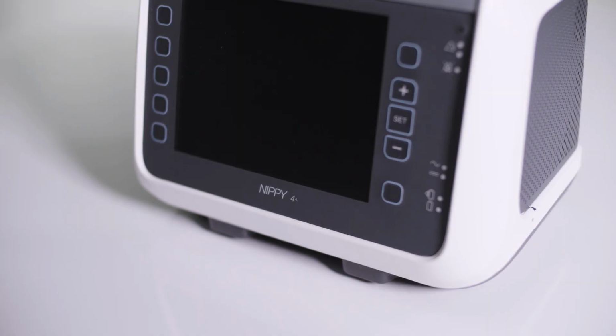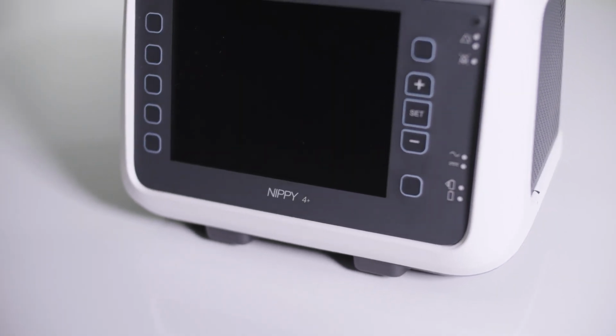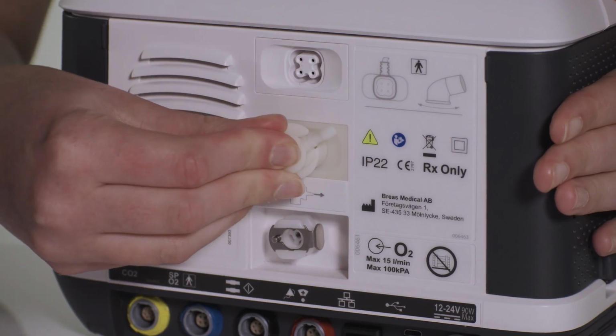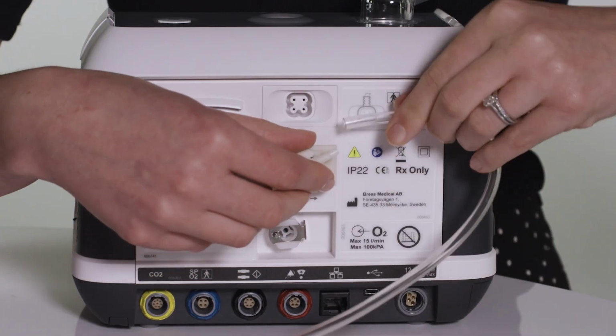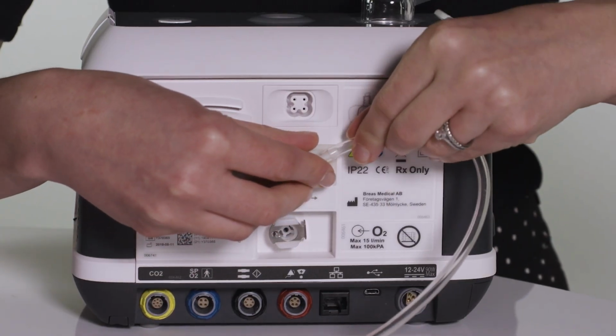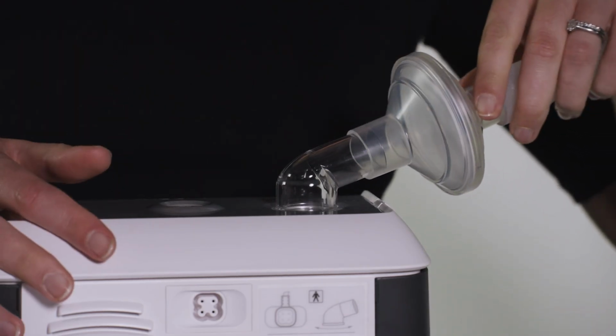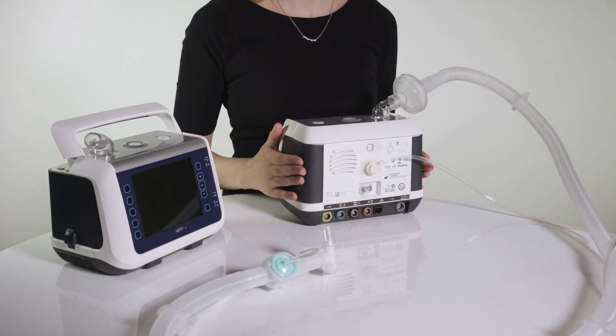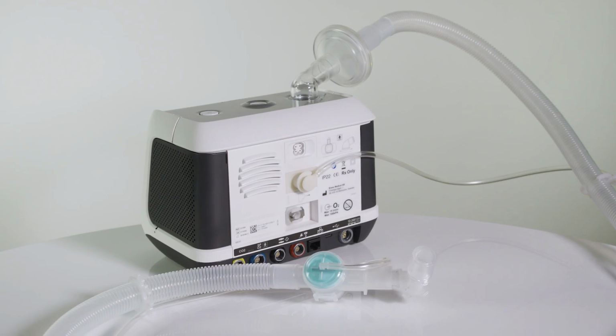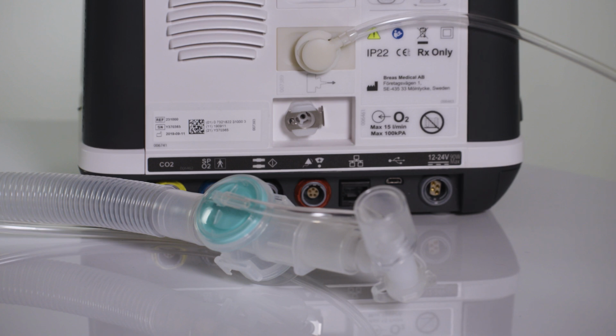Active circuits, Nippy 4+ only. When using an active valve circuit, you would need to attach the Nippy 4+ pilot line connector to the rear of the ventilator. Unlike leakage circuits, these have an active exhalation valve, which is controlled by an additional pilot line, which runs down the outside of the breathing circuit.